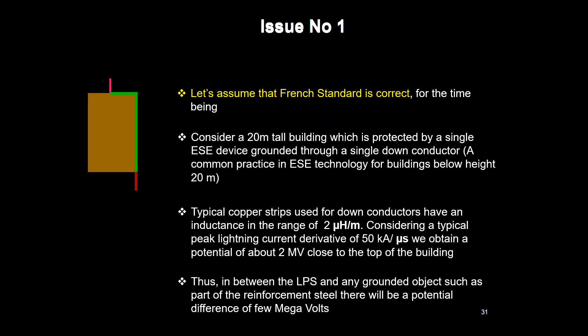Don't forget that when we are considering the calculation, it is not the height of the building that comes into the picture, because when you are having a down conductor, there are so many bends and horizontal paths going from the edge of the building to the air termination. So the real length of the conductor may be 20-30% higher than the height of the building. So there is a fat chance of a large voltage drop along the conductor, and towards the top of the building the voltage can be extremely high. So in plain words, even if the air termination attracts the stepped leader as the ESE vendors claim, there can be arcing.